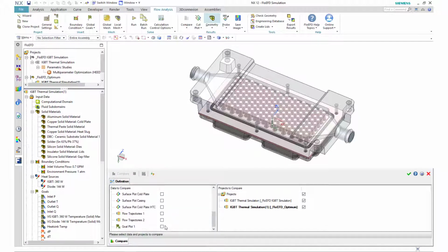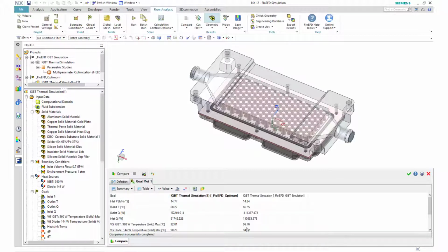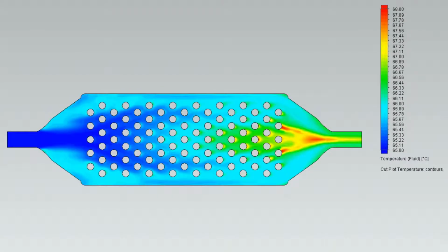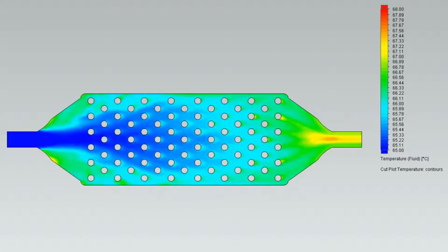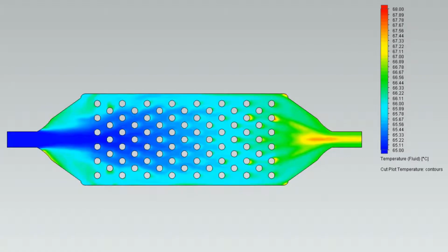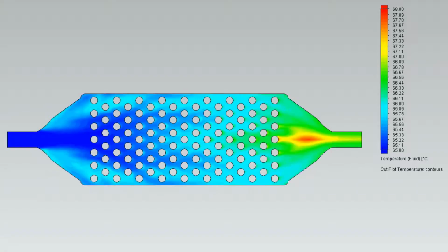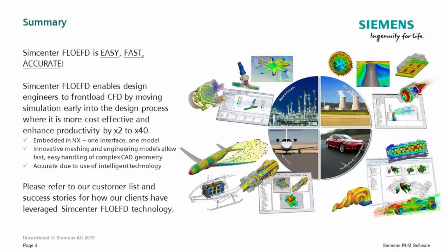We can also use the numerical data to compare the results. From this table, we can see clearly that our maximum temperature drops and the delta P decreases as well. Performing this parameter study, we can obtain not only one, but several optimum designs, allowing the user to take this newfound knowledge to look into the possible trade-off of IGBT maximum temperature and pressure drop of the cooler.